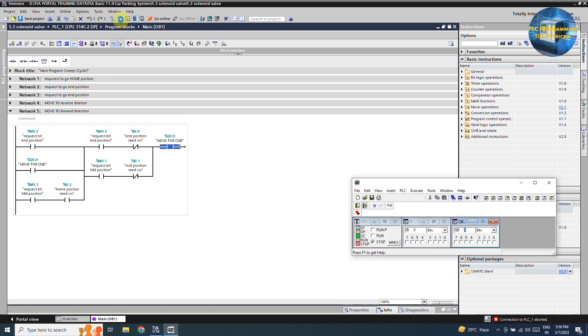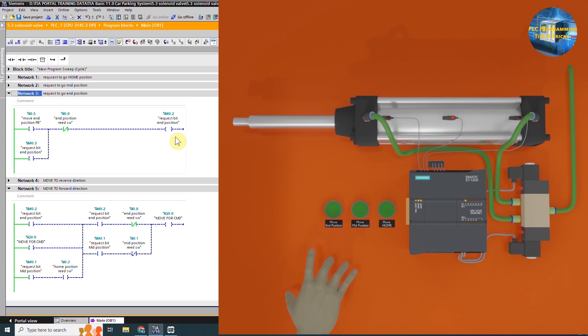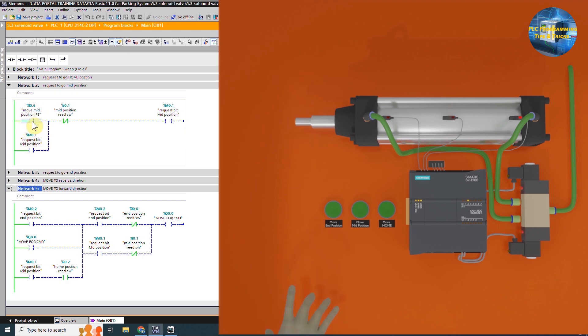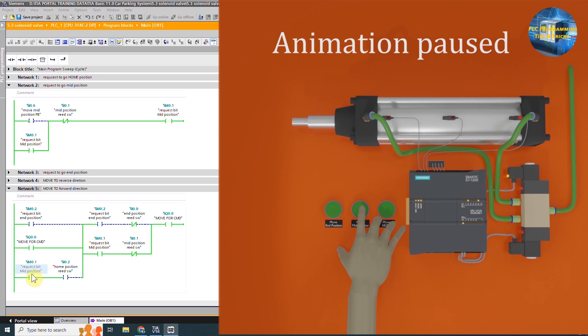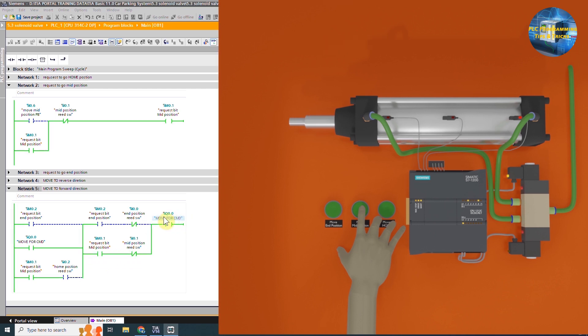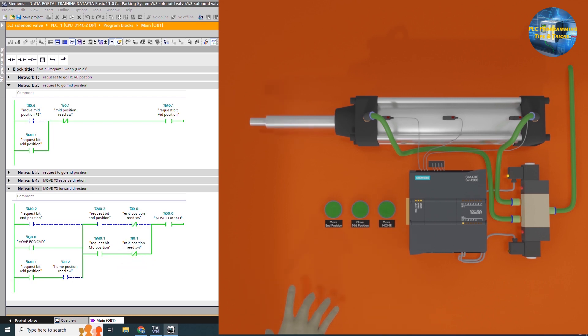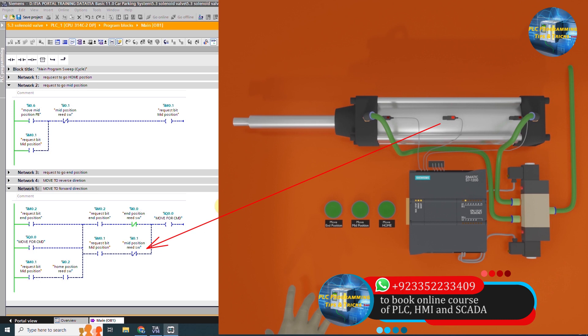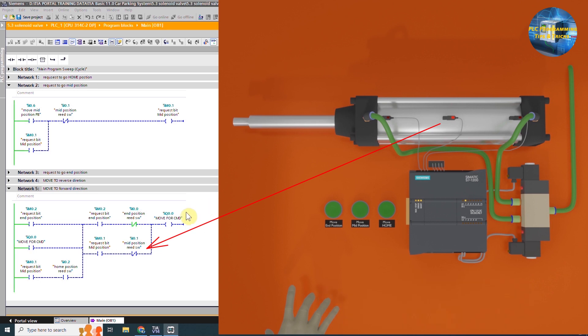Next we will upload the ladder logic to the PLC and see how it works. Right now the cylinder is at the home position, so its home reed switch i0.2 is on. As we press the mid position push button, the mid position request bit m0.1 latches on. In network 5, the m0.1 bit latches on the forward command output Q0.0 and the cylinder starts to move forward. As soon as the cylinder reaches the mid position reed switch i0.1, this contact opens and turns off Q0.0 and the cylinder stops at the mid position.